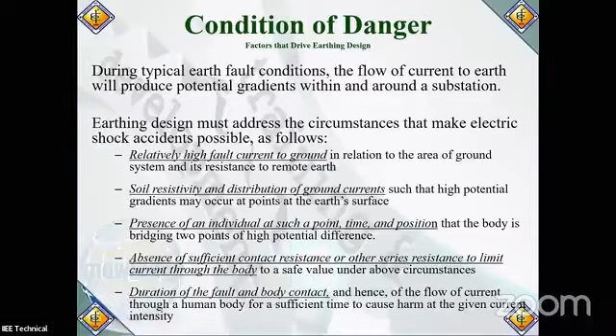And that is what IEEE 80 is all about - being able to determine, number one, what is the maximum that the body could tolerate between the feet and the touch, and what are the safe levels that has to be determined for a certain body, female or male, to be able to survive. Kasi pag hindi mo na kaya nun, death will happen, sigurado. And meron din, duration of the fault and body contact - these are what we call the design parameters. Duration of fault, and hence the flow of current throughout the human body for a sufficient time to cause harm at the given current intensity. Medyo critical yung duration of fault. So these are the conditions of danger.